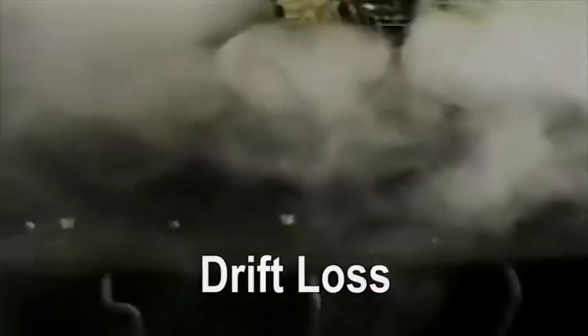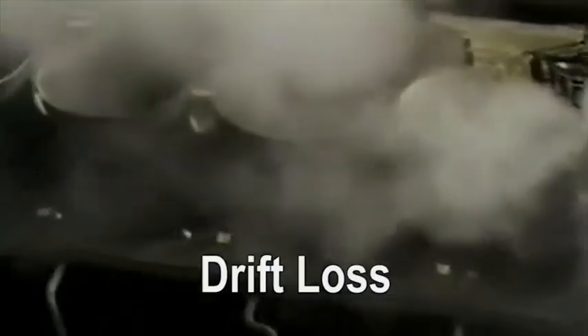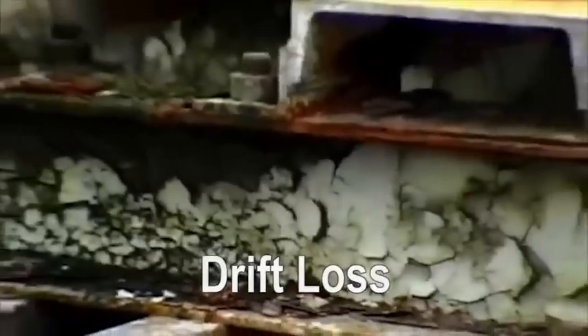Another side problem resulting from high-velocity airflow is enhanced drift loss, which wastes significant volumes of water. In most facilities, makeup water is as precious as fuel. Increased drift loss also corrodes and contaminates adjacent equipment. In areas where water loading is light, evaporation accelerates, causing premature fouling of the fill media. This increases service and maintenance costs.